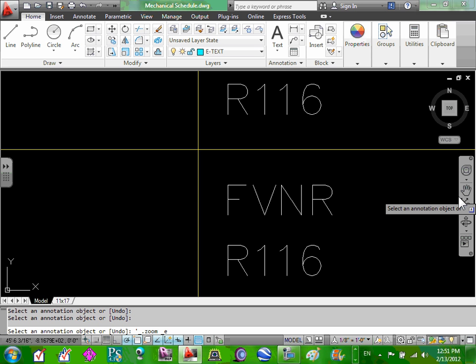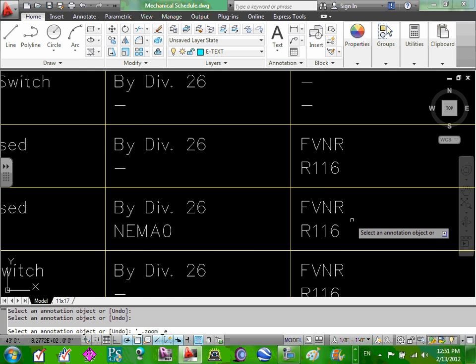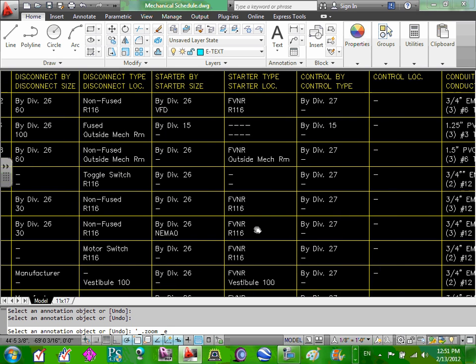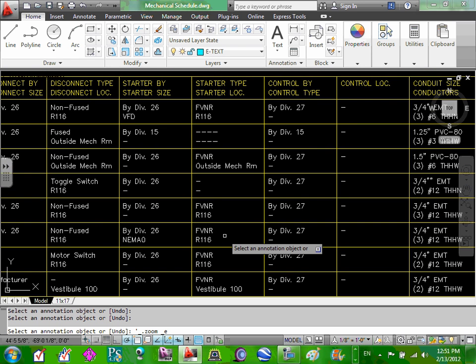FV stands for full voltage, non-reversible. What's the alternative? Full voltage reversible, if you need to reverse the motor. They didn't tell us anything about reverse. Okay? Where it's located, the type, the size, starter size, it's going to be located in room 116 because the disconnect and the pump are in room 116. If you don't know where it's going to be located, it's always located where the equipment is located.